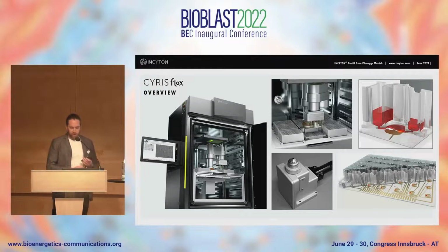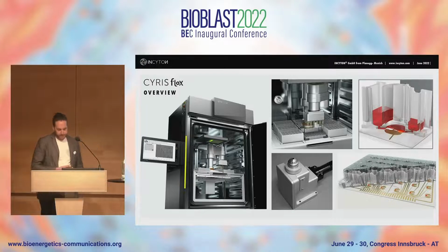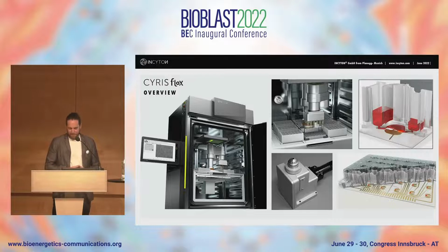The technology in detail is built within an atmospheric chamber, where we have an incubator and quite a lot of technology inside. We control temperature, humidity, and the oxygen content from 1% to 21%, which is normoxia, depending on the ABC of hypoxia. Inside the chamber, there is a robotic system that supplies media and drugs to our living cells in our special sensor well plate.